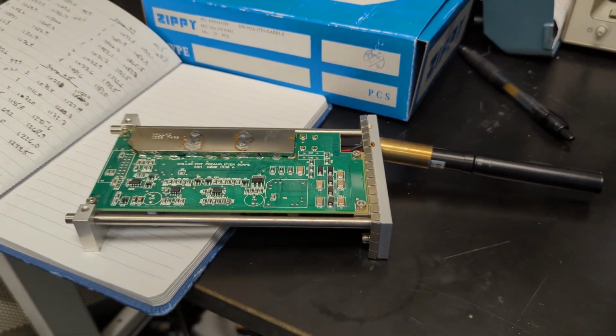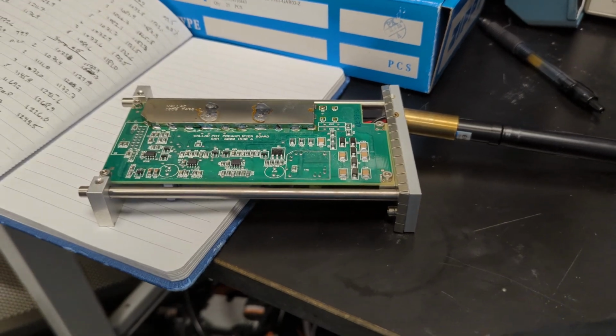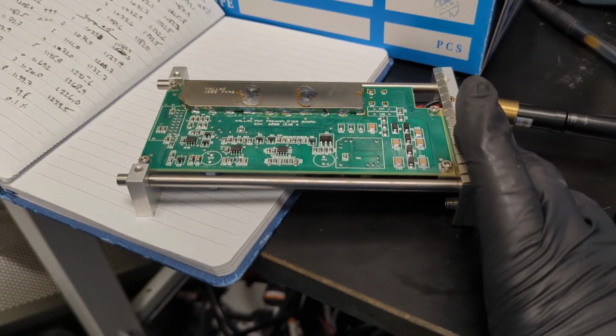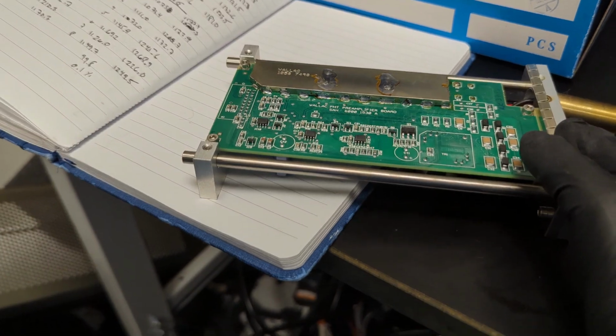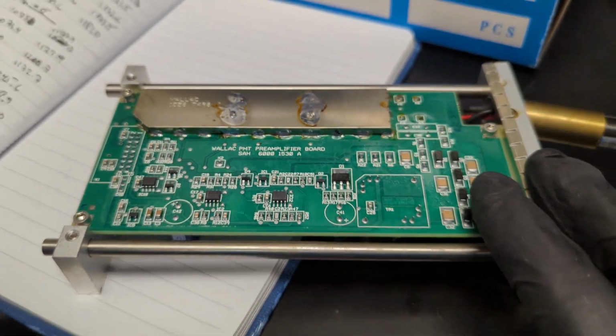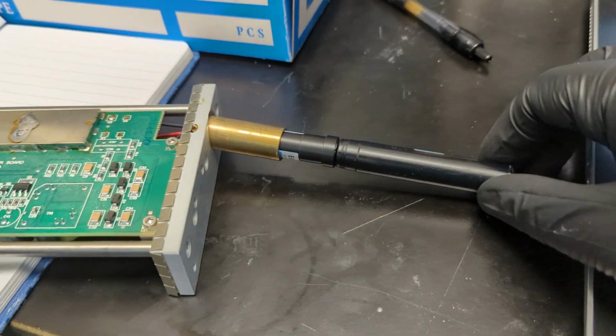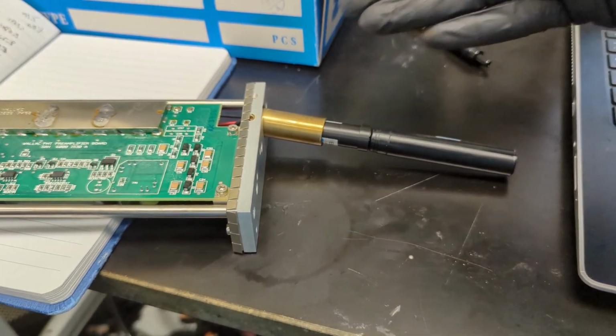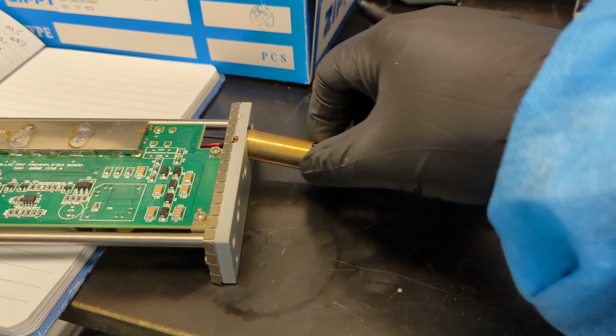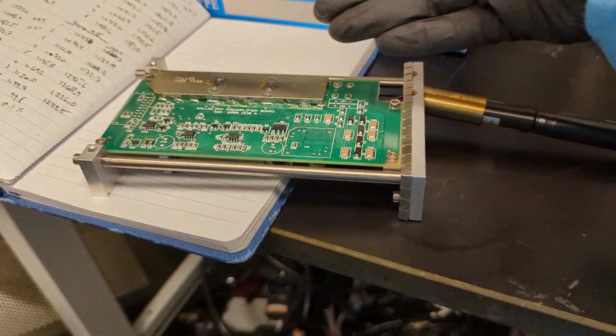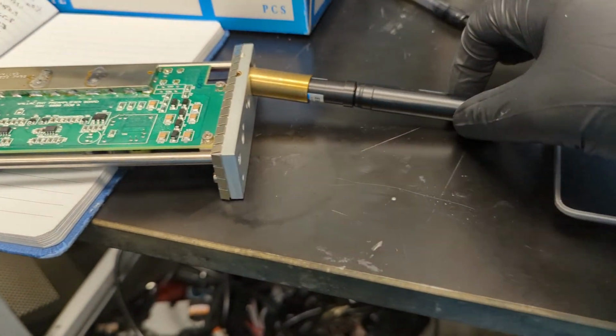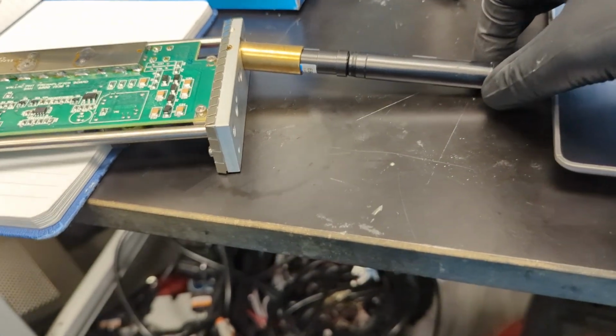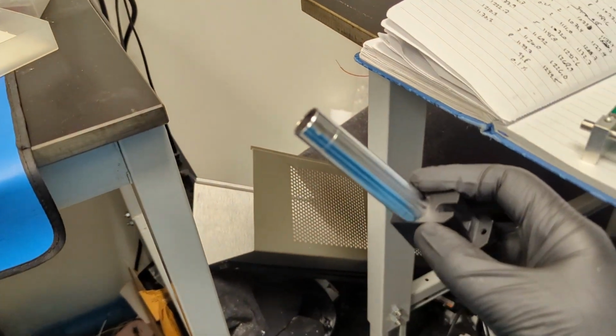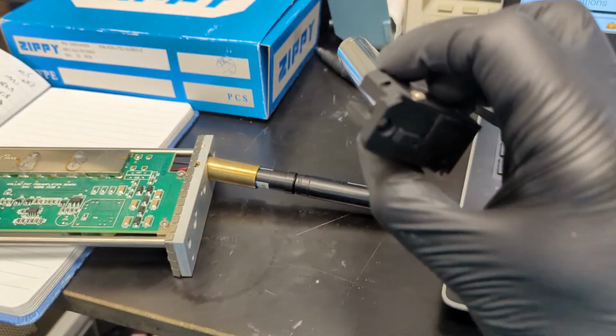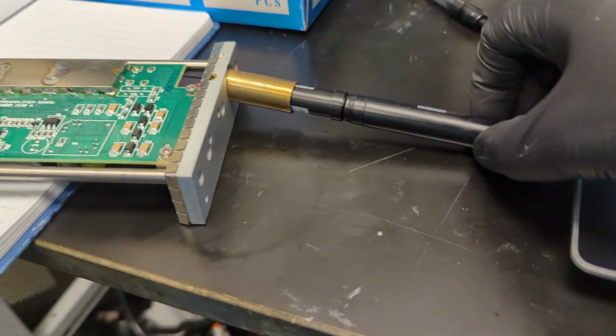Alright, so I thought we could take a closer look at the detector for one of these instruments. Now this is actually an ultra sensitive luminescence detector that I pulled out of one of these guys, and you can see it says PMT preamplifier board on it, but this is actually the PMT. Now I believe you might have got a quick glance of this, but for the ultra sensitive luminescence detector, there's this pipe that runs down to, yeah, here it is actually. So this pipe is what the PMT sits in. Let's take a look at the circuitry. So, well, actually, let's start with the PMT.